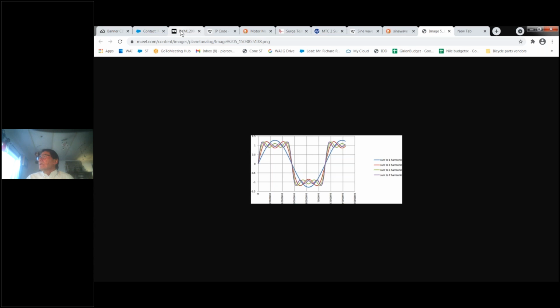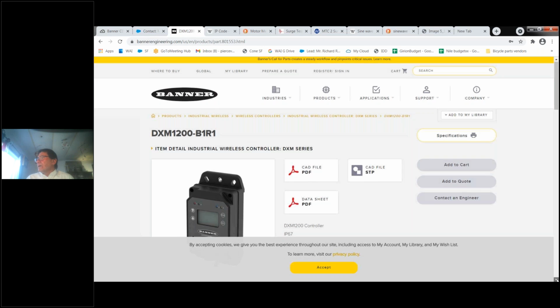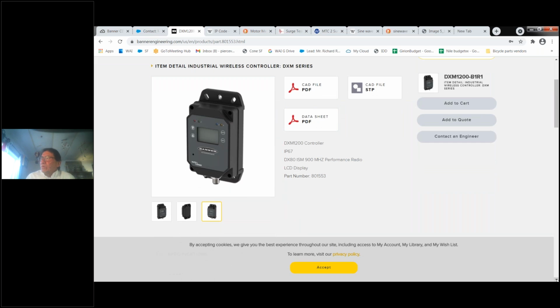What we're talking about is a device that looks something like this. This happens to be a weatherproof unit, IP67, meaning you can dunk it in 1 meter of water. So it's very suitable for just sticking on the side of the VFD can. I put a sunshade on it because ultraviolet will eventually damage that screen. And you wire it directly to the VFD via a Modbus serial connection.